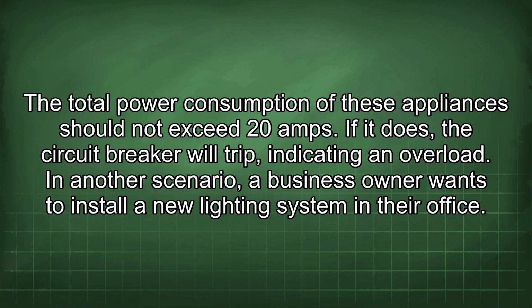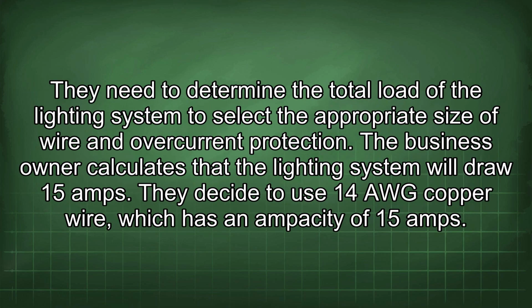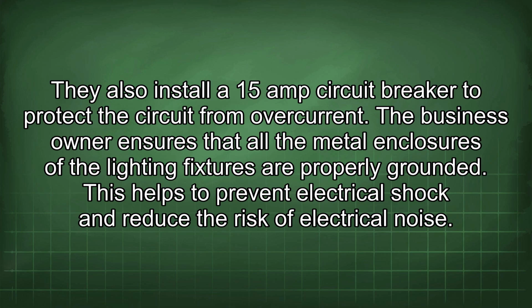In another scenario, a business owner wants to install a new lighting system in their office. They need to determine the total load of the lighting system to select the appropriate size of wire and overcurrent protection. The business owner calculates that the lighting system will draw 15 amps. They decide to use 14 AWG copper wire, which has an ampacity of 15 amps. They also install a 15-amp circuit breaker to protect the circuit from overcurrent. The business owner ensures that all the metal enclosures of the lighting fixtures are properly grounded. This helps to prevent electrical shock and reduce the risk of electrical noise.